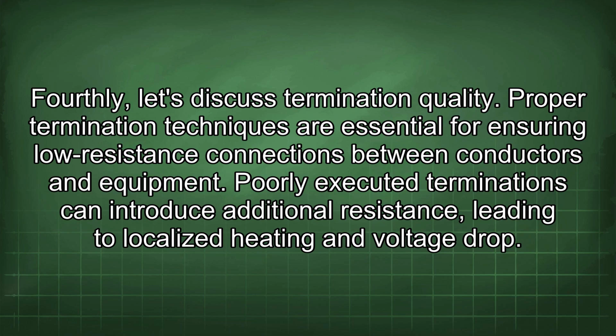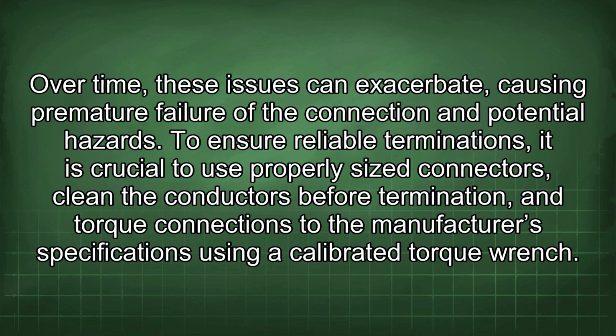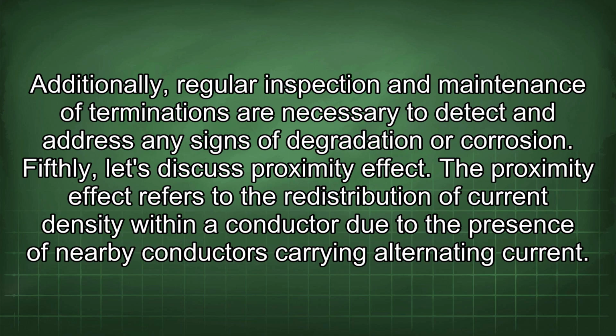Proper termination techniques are essential for ensuring low resistance connections between conductors and equipment. Poorly executed terminations can introduce additional resistance, leading to localized heating and voltage drop. Over time, these issues can exacerbate, causing premature failure of the connection and potential hazards. To ensure reliable terminations, it is crucial to use properly sized connectors, clean the conductors before termination, and torque connections to the manufacturer's specifications using a calibrated torque wrench. Additionally, regular inspection and maintenance of terminations are necessary to detect and address any signs of degradation or corrosion.